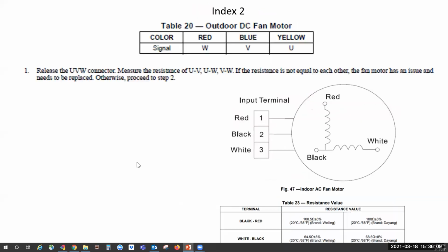Now this is the second motor. This one's a 3-wire motor, and on this one the chip is in the control board. This one will ohm out like a 3-phase. On all of this, when you're ohming these things out, on the 5-wire and the 3-wire, even on the compressor, do not forget to check for signs of overheating and also check for ground.